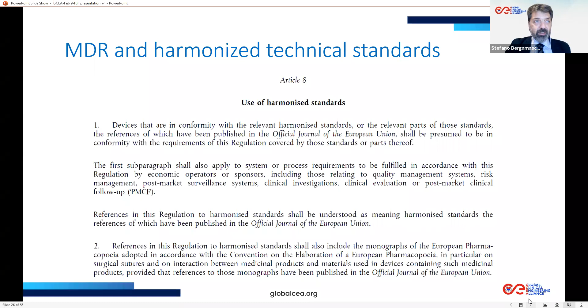However, we need technical standards to know, as manufacturers, for example, the technical solutions that respond to the state of the art. Inside the regulation, this article says that if a device is in conformity with the relevant harmonized standards, then they shall be presumed to be in conformity with the legal requirements of the regulation. So there is a presumption of conformity. The key element here is that the technical standards are not mandatory. A manufacturer may choose a different technical solution than what is stated in a technical standard. However, they set the state of the art and are the best way towards conformity. So this is the use of technical standard.